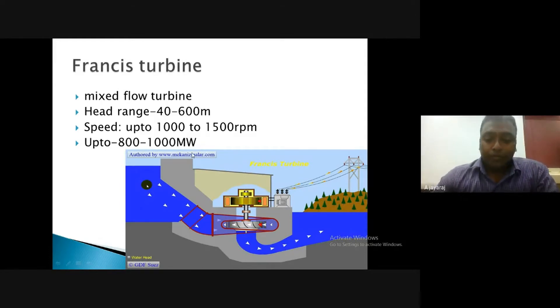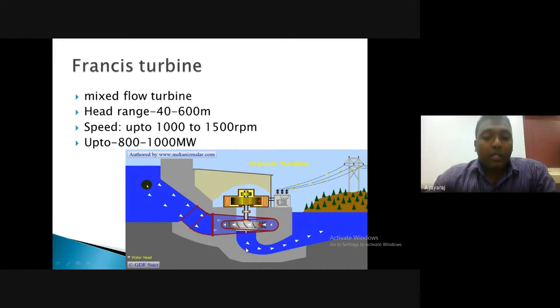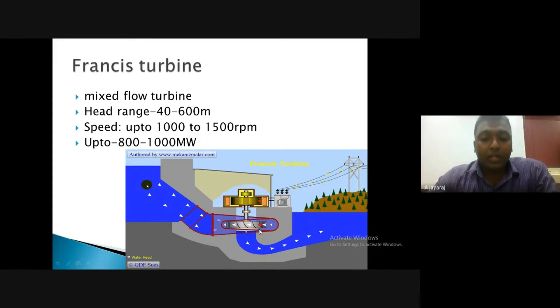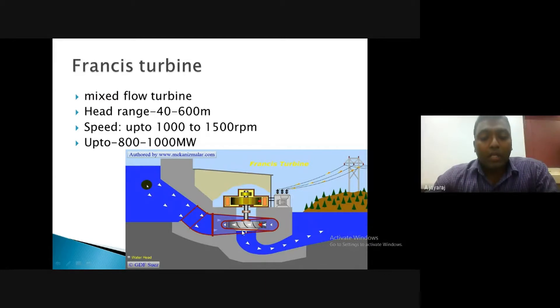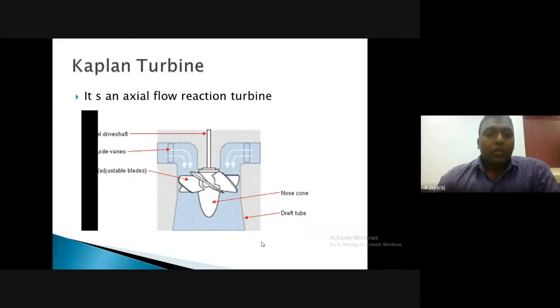Regarding the Francis turbine discussed in our previous class: it was a mixed flow turbine where flow enters radially and leaves axially. The head range for Francis turbine is typically 40 to 600 meters, and the speed is up to 1000 to 1500 rpm. The power output obtained is up to 800 to 1000 megawatts with a modern Francis turbine.